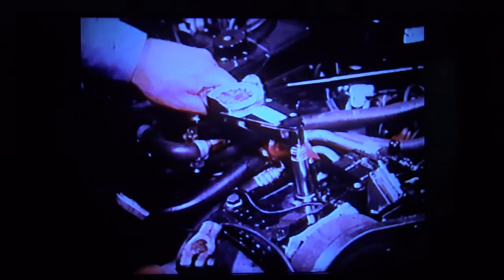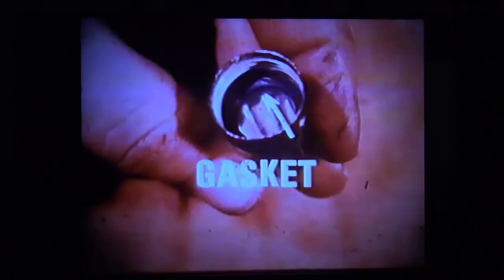Inspect the O-ring on the oil filler plug for damage and replace if necessary. Then install and torque the plug. Open the suction service valve slightly for about 10 seconds to allow air in the compressor to bleed from the discharge service port. Then tighten the discharge service valve port cap and fully backseat both service valves.